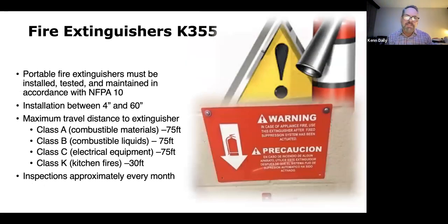Fire extinguishers: you have fire extinguishers throughout your corridors. They should be within 75 feet of each other throughout the corridors. In America, we use the ABC type extinguisher, which is very common. Then in the kitchens, where there's a potential grease fire, you'd use what's called a K type extinguisher, whose contents are appropriate for grease fires. That must be within 30 feet, so everybody is within 30 feet of a K-type extinguisher. Sometimes you might need a second one in the kitchen. Some kitchens are pretty large, and 30 feet is not as far as you think.